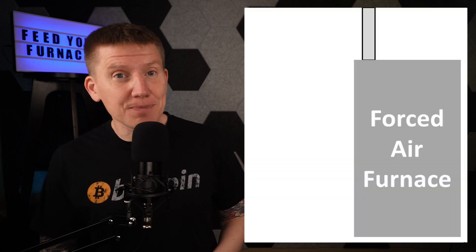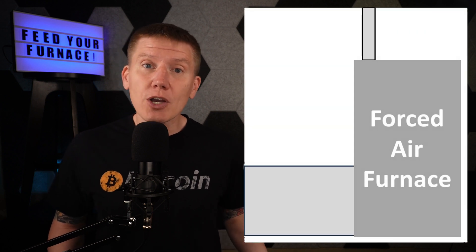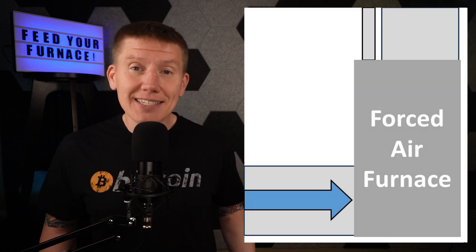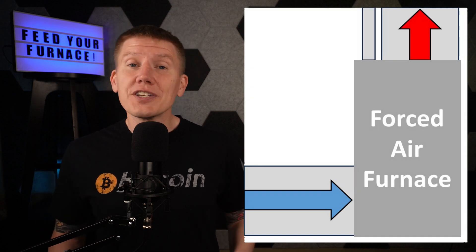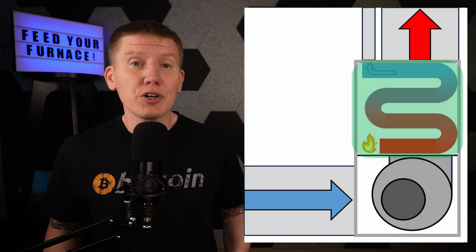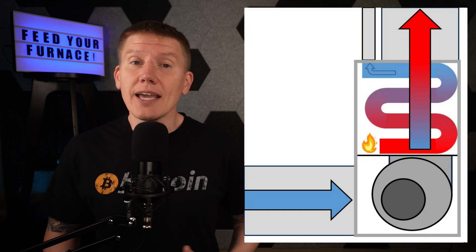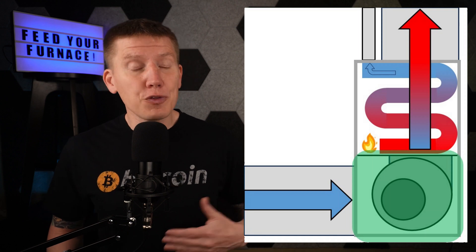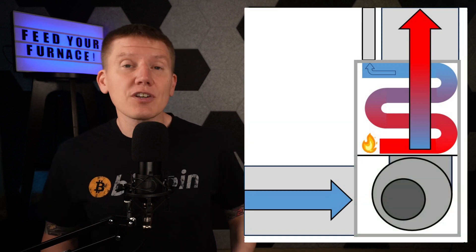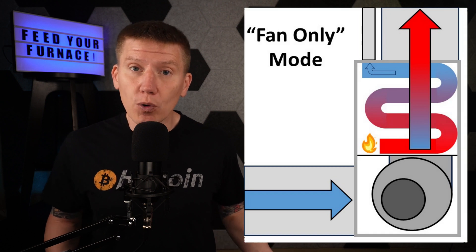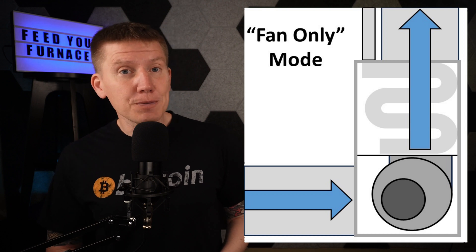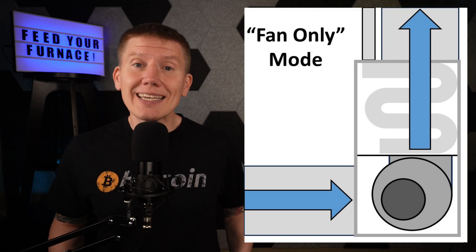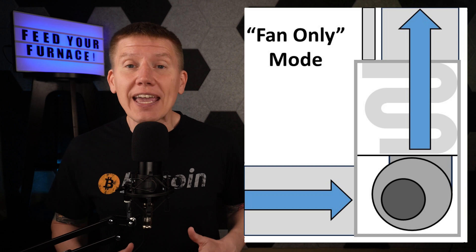For this setup, we'll start with an existing forced air furnace. This type of furnace has a return side plenum where the cold air enters the furnace and a supply side plenum where the heated air exits and flows to your house. The furnace consists of a burner and heat exchanger that work together to heat up the air, and a large fan which forces that air through the house. All furnaces are designed to run in a fan-only mode where the burner is off but the fan is turned on to circulate air through the house.